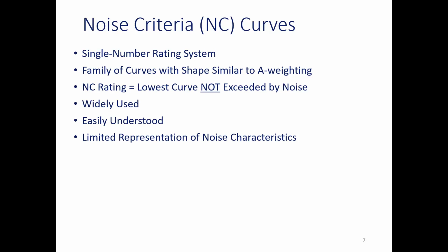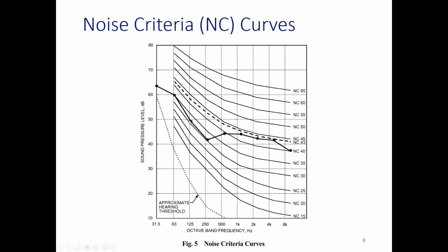The NC rating of noise in a space is the lowest curve not exceeded by the noise. So again, if we come here, the dots are the noise measured in that room or predicted in that room. So you want to find the curve. You're not going to have something like a 42.6 NC. It's always going to be an integer. Here, 43 is the lowest NC curve that's not exceeded. So that would be the NC level for the space. This point right here is what's dictating the NC level.